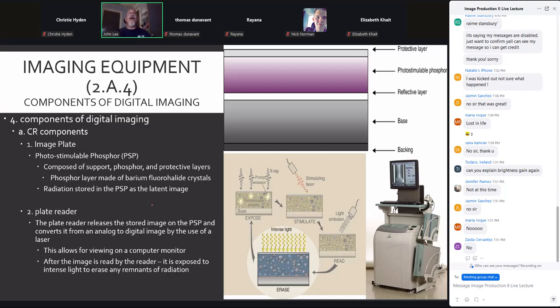These systems require a plate reader. Now, the plate reader, in addition to pulling the energy out of the phosphor, pulling it into the computer, adjusting the signals, giving us our digital image, it is responsible for erasure of the plate, which is just a very, very intense white light that resets the phosphor, provided that we didn't give a lot of exposure to it the first time we used it. Thousands of exposures can be made on these image plates if you take care of them.